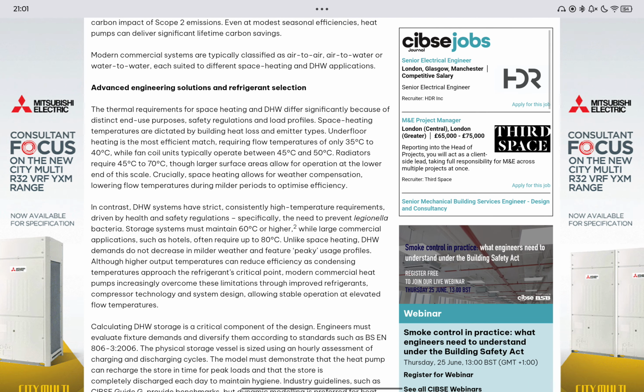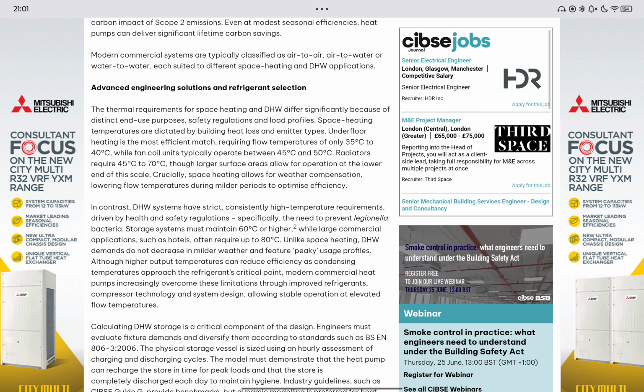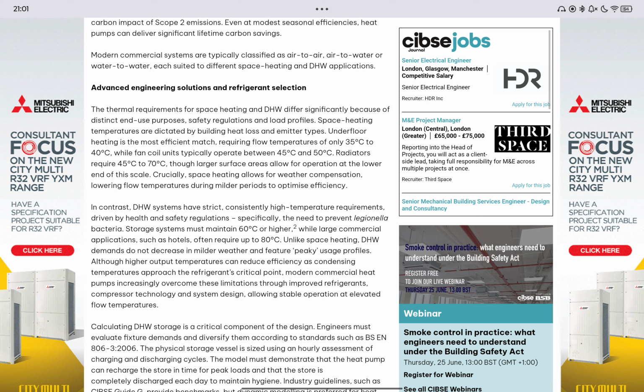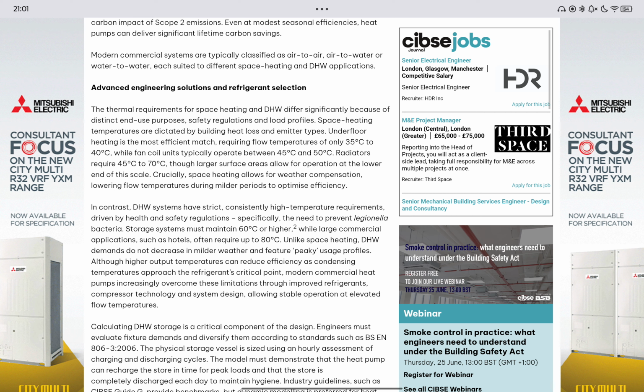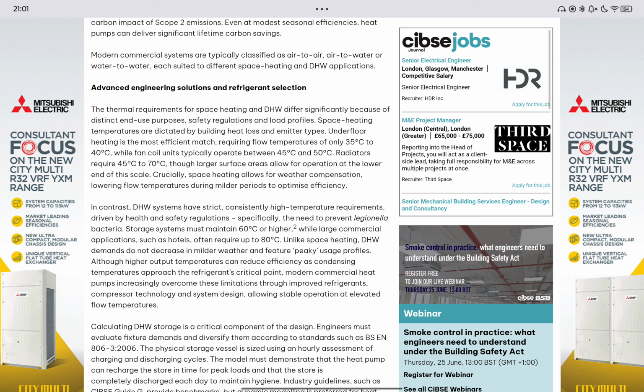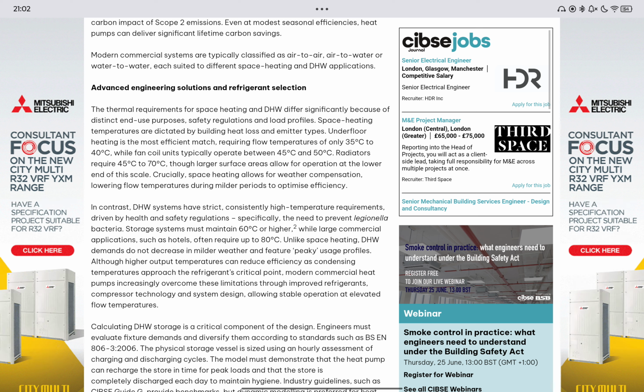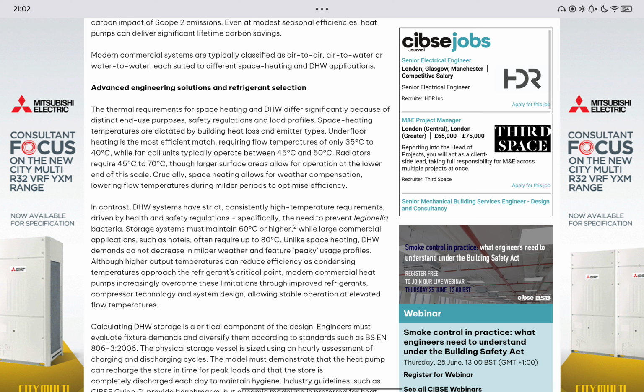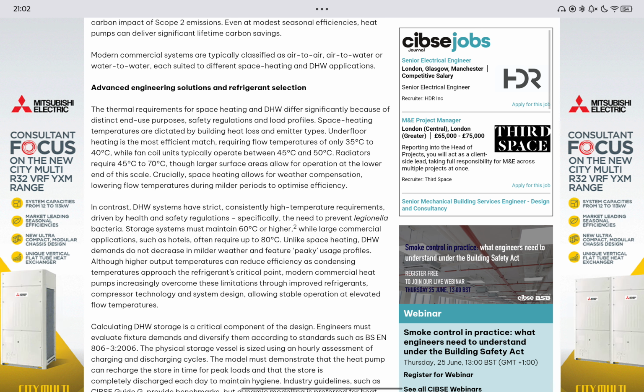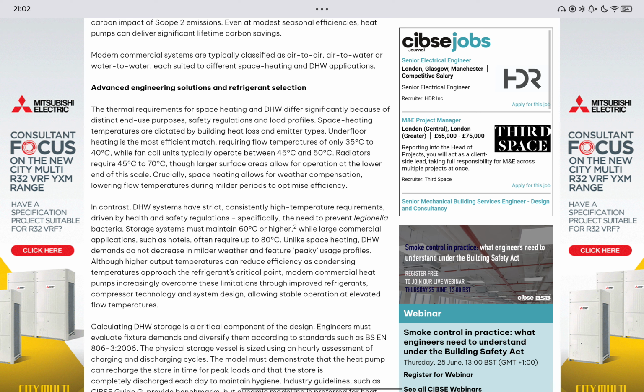Advanced engineering solutions and refrigerant selection. The thermal requirements for space heating and DHW differ significantly because of distinct end-use purposes, safety regulations and load profiles. Space heating temperatures are dictated by building heat loss and emitter types. Underfloor heating is the most efficient match, requiring flow temperatures of only 35 degrees C to 40 degrees C, while fan coil units typically operate between 45 degrees C and 50 degrees C. Radiators require 45 to 70 degrees C, though larger surface areas allow for operation at the lower end of this scale.